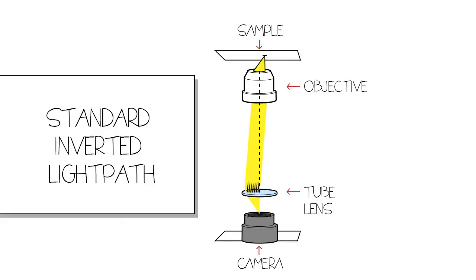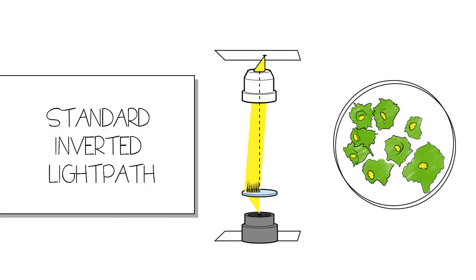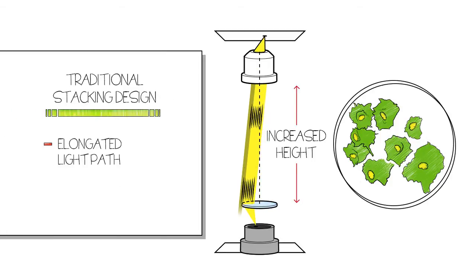This increase in height leads to elongation of the light path. Consequently, image quality can be compromised because some of the light cannot reach the tube lens. This leads to a smaller field of view and vignetting in the camera ports.